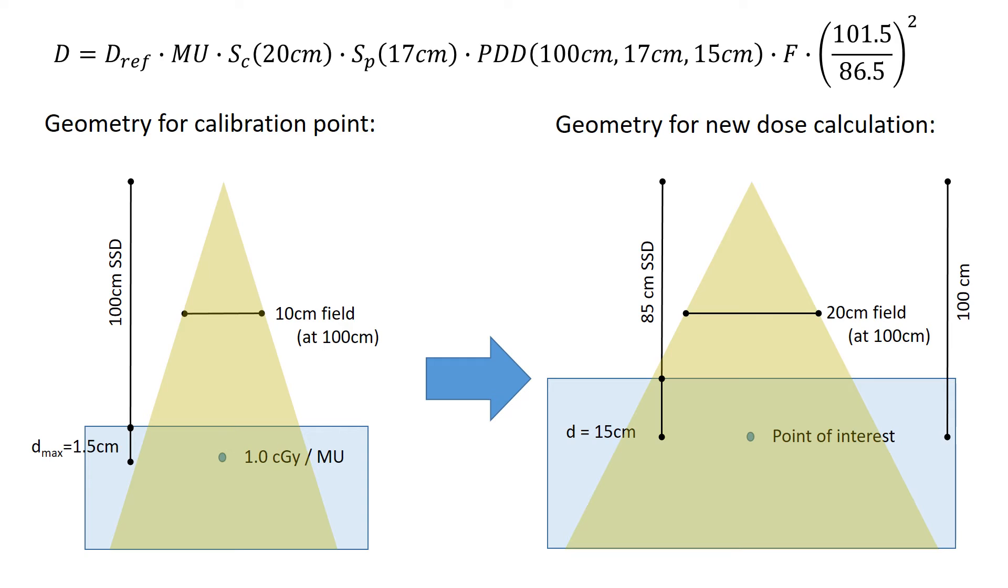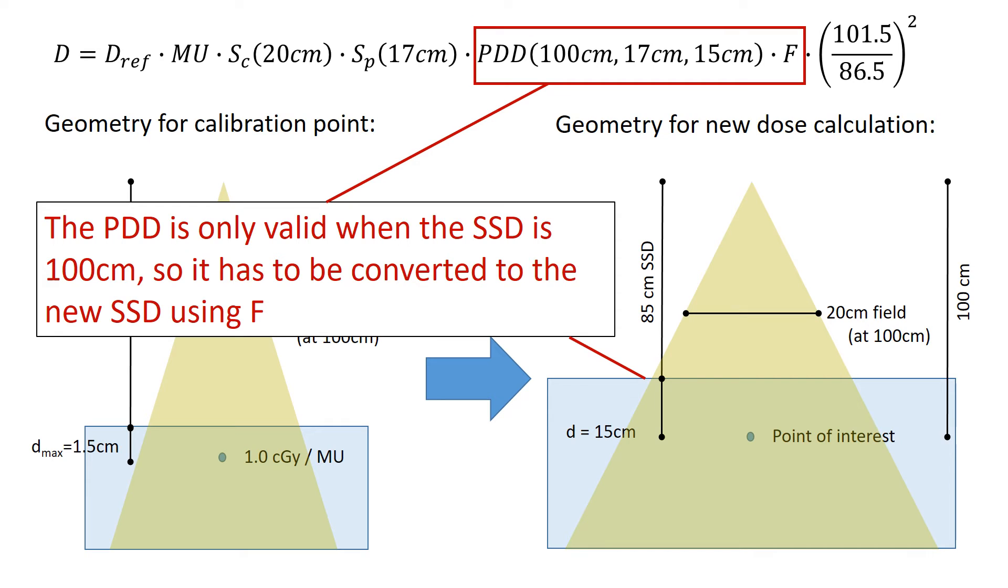Now let's look a little closer at the PDD. So our PDD is only valid for a source-to-surface distance of 100 cm. And so we actually have to convert the PDD that we have to be valid for another source-to-surface distance. And we do that using a factor called f, and that's this other factor that's here next to the PDD. So we can look up our PDD, but it's not really valid until we apply f for any SSD other than 100 cm.